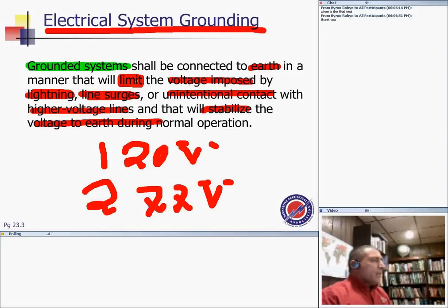Electrical system grounding would require, I believe, anything higher than 50 volts to be grounded. If you have any system higher than 50 volts, it has to be grounded. For industrial applications, they allow you to use ungrounded systems.